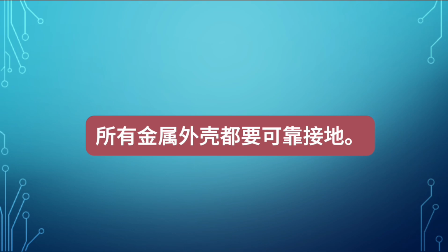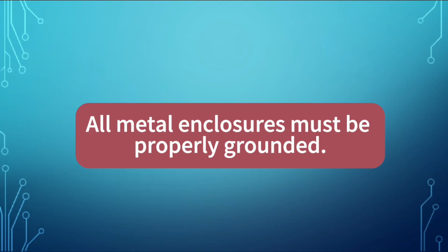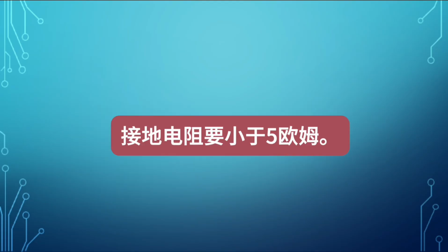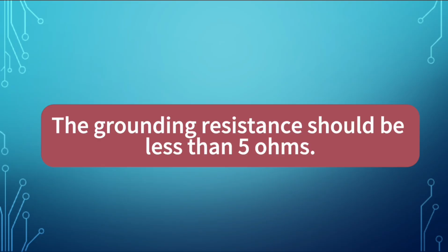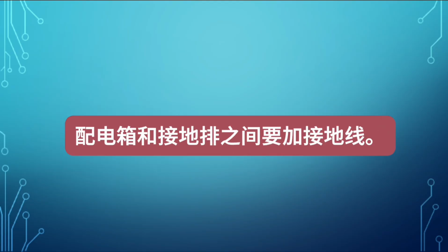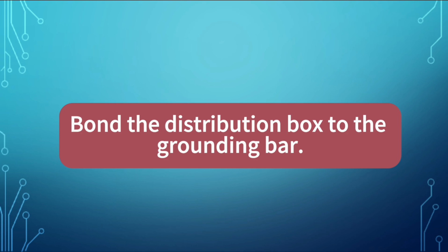All metal enclosures must be properly grounded. The grounding resistance should be less than 5 ohms. Bond the distribution box to the grounding bar.